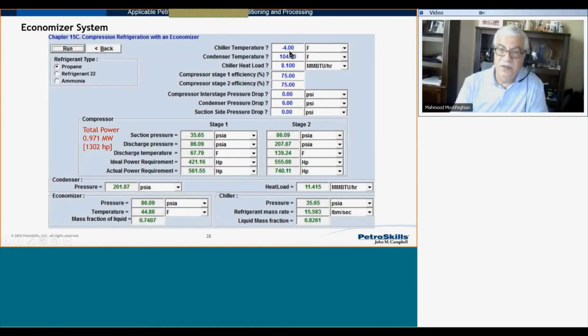The input information is the same as before, except we have two stages of compression, so we have two efficiencies, which are kept the same. Pressures are kept the same. So the program calculated first stage compression, second stage compression, first stage power requirement 561.55, second stage 740. If I add these two power requirements, the sum would be 1,302 horsepower, and that compares much lower than 1,533 that we obtained for simple refrigeration system. Again, we will see a summary table later on to make the comparison.